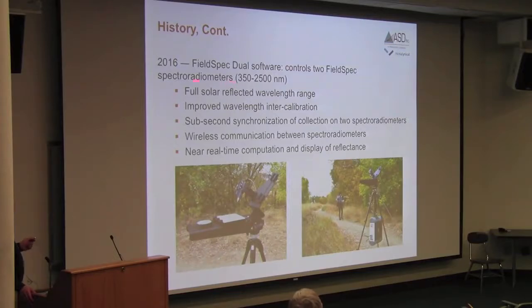So this is software we finished up just very recently that automates this whole process, and it covers the full wavelength range. Besides seeing the paper come out that shows that this would work, we also realized that there's a large install base of our instruments out there, and if we could do a software solution, people wouldn't have to buy a new instrument to do this. They would just need to get 2 instruments together, and as long as they had similar wavelength spectral resolution profiles, you could use them together.